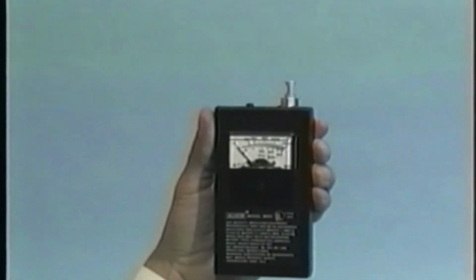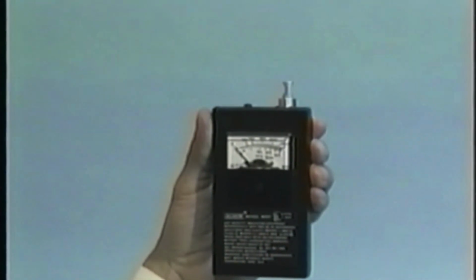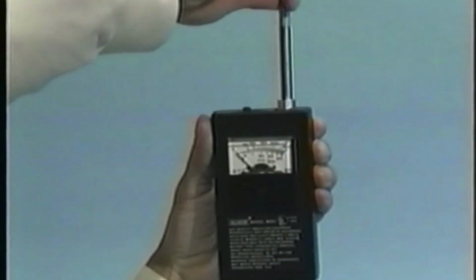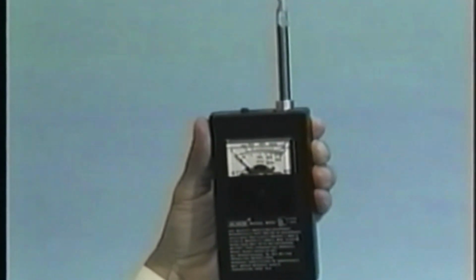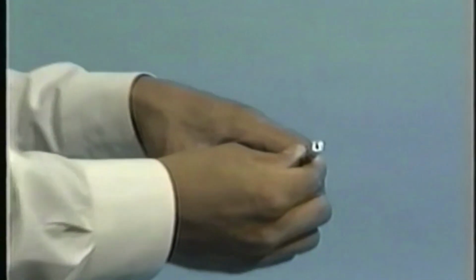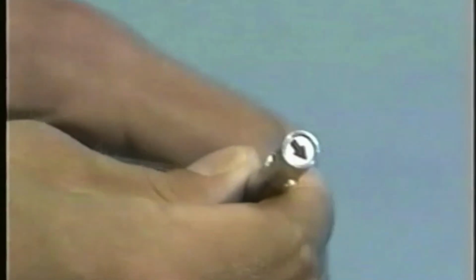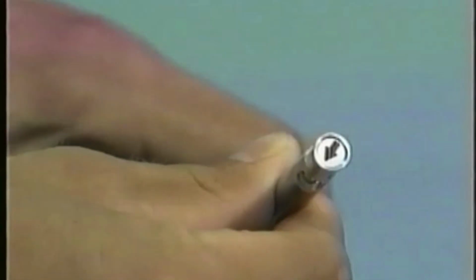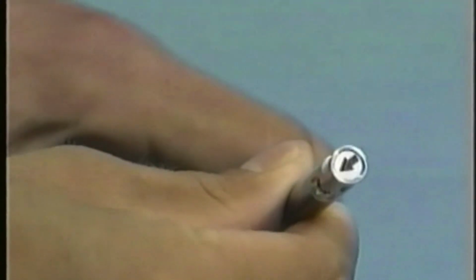To use the probe, simply grasp the tip and slide it to the fully extended position. Once it is fully extended, it can be rotated 180 degrees, and the meter can easily read airflows coming from various directions. When in use, the probe must be turned so that the airflow is in the same direction as the arrow on the top of the probe.